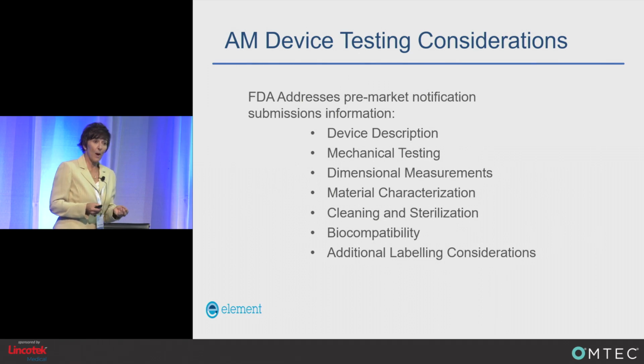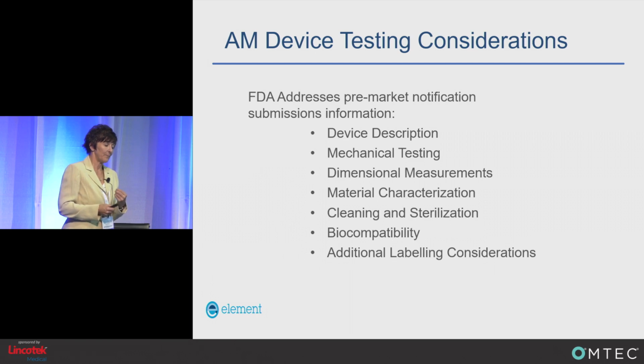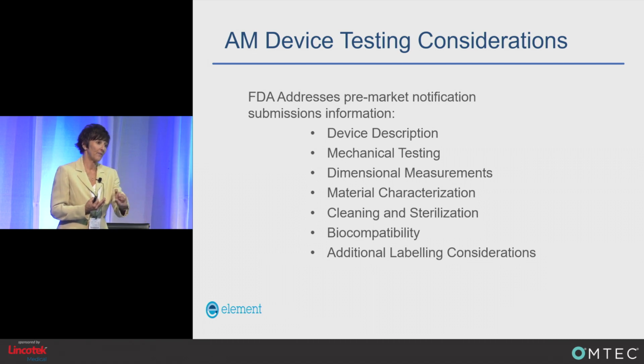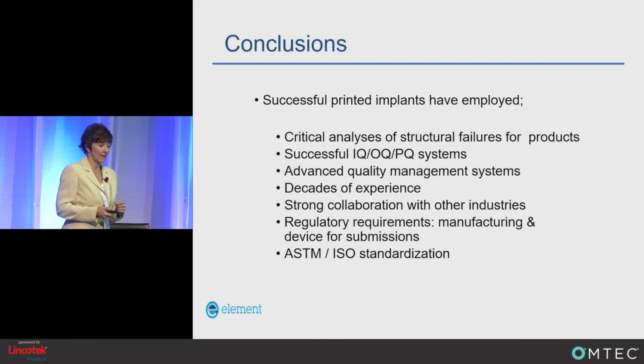From the manufacturing processing side, they also want you to provide the device description. Understand that description. What about the mechanical testing? Have you addressed not only the device itself, but also the coupon testing for your manufacturing process that would be required by the FDA as well? Assess the dimensional measurements. Where are your tolerances? Are they within that range, although it's a broader range? What about the material characterization as well? The cleaning, sterilization, and biocompatibility are for your 510(k)s.